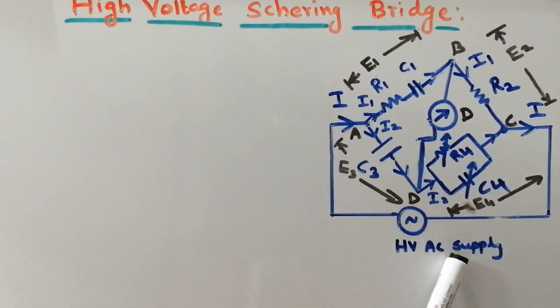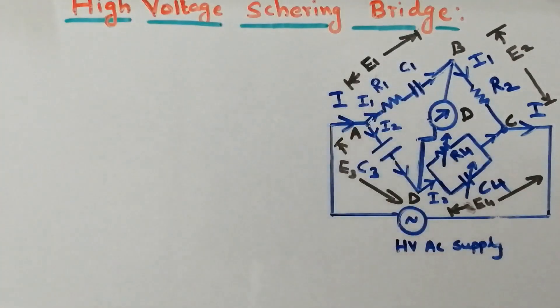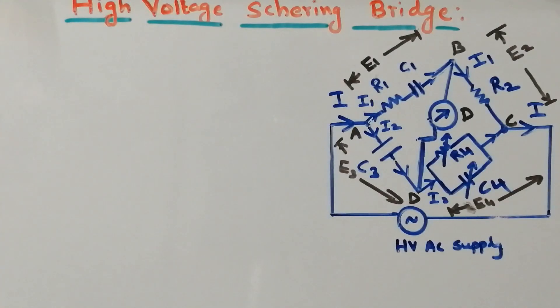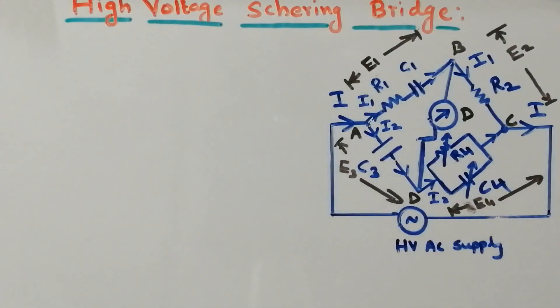We have high voltage AC supply over here. Let us familiarize the different components of respective arms. R1 and C1 represent the equivalent circuit of insulation material. R2 represents a non-inductive resistor. C3 represents the standard value of capacitor, or you can call it a condenser. R4 and C4 are the variable resistor and capacitor respectively. Now, let us consider a cable and its insulator, which are represented by arm R1 and C1.